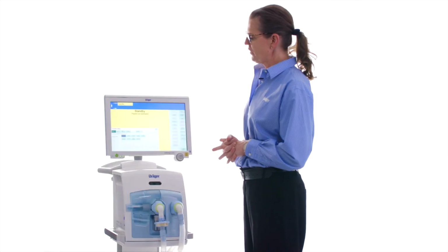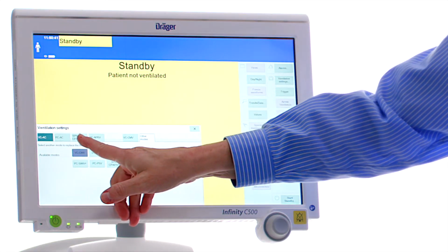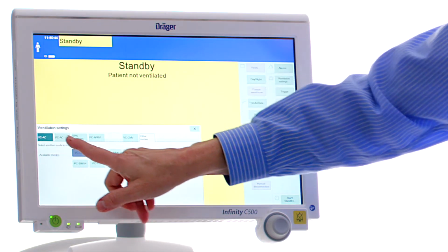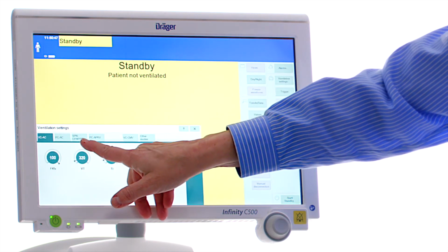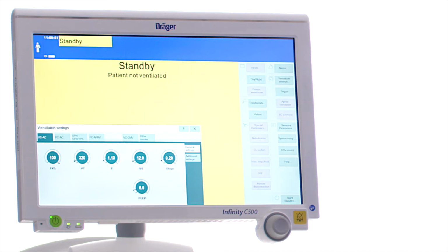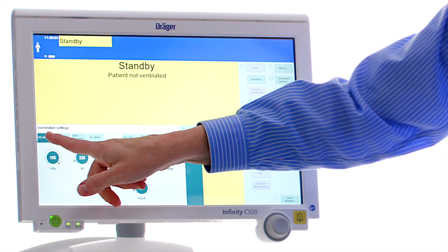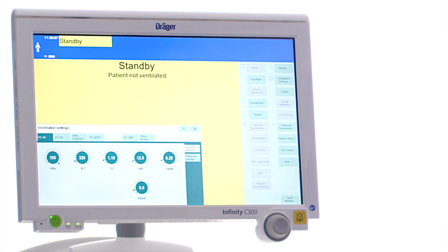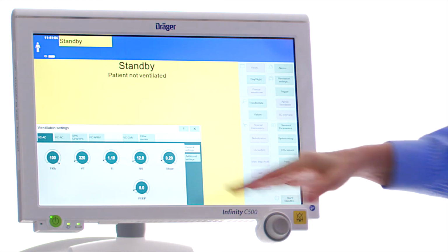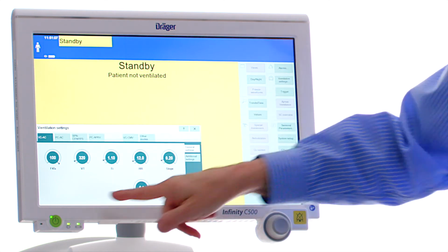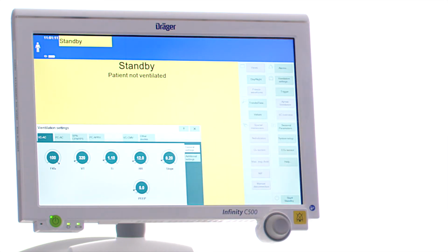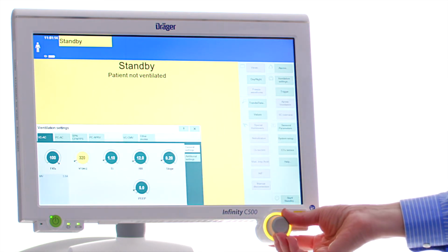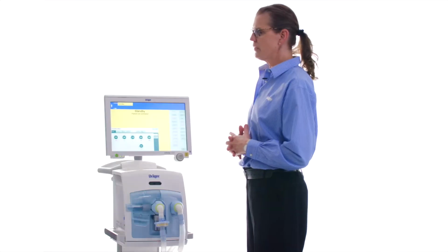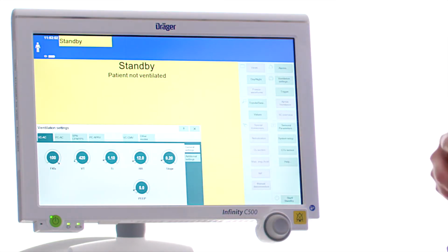To decipher the nomenclature on this ventilator, each mode of ventilation will have a prefix. We have VC for volume control, we have PC for pressure control, we have SPN for spontaneous breathing. Following the prefix, the mode sequence, assist control, SIMV, pressure support, makes it easy for the user to identify what type of breath is being delivered to the patient. Below your modes of ventilation, you have all of your basic ventilation parameters in the General Settings window. Again, touch the button, turn the rotary knob, and confirm. Touch, turn, confirm is the most important part of making changes on the Draeger ventilator. You have your basic parameters that sit under the General Settings tab.